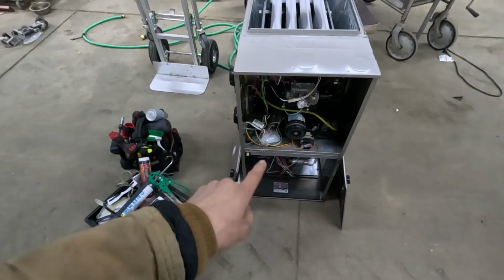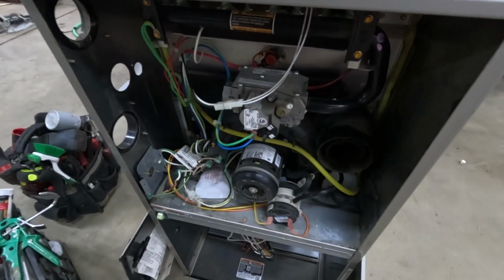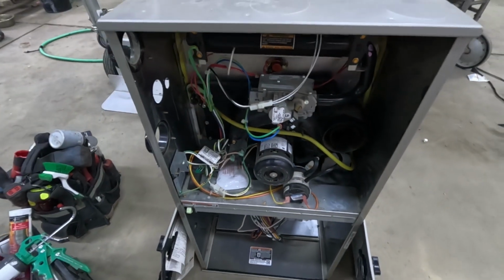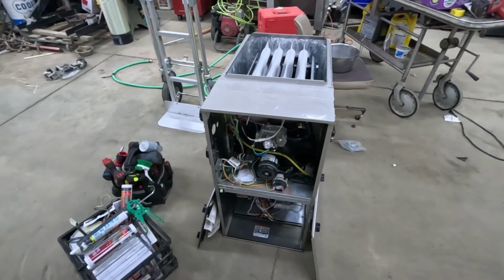It's a little unusual that this one went bad so quickly. We think it might have been due in part to the gas pressure at the location being incorrect, so we replaced the regulator there just to make sure that wasn't the cause. It was running LP, and we've found that LP furnaces typically have their heat exchangers go bad sooner than natural gas ones — maybe because of the amount of mercaptan in the propane. I'm not really sure.